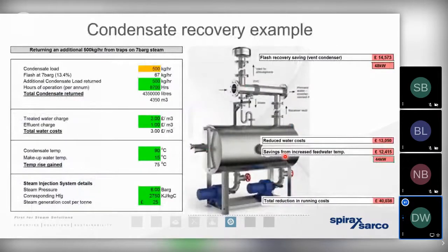So it's important to give thought to not only recovering as much of that liquid condensate as we possibly can, but also minimizing that flash steam that's vented to atmosphere. And we can minimize that flash steam that's vented away by allowing the condensate to subcool slightly. And that's going to result in a lesser volume of flash steam being vented away. But even when we do need to vent that flash steam away to protect capital equipment, such as an electric condensate receiver, by passing it across an exhaust vent condenser, it means that we can at least increase the mass of condensate that can be recovered and returned back to the boiler house.